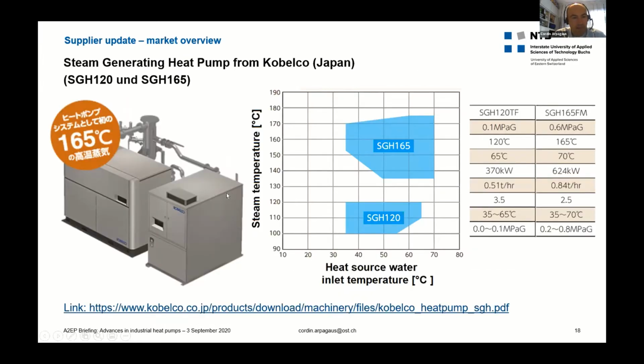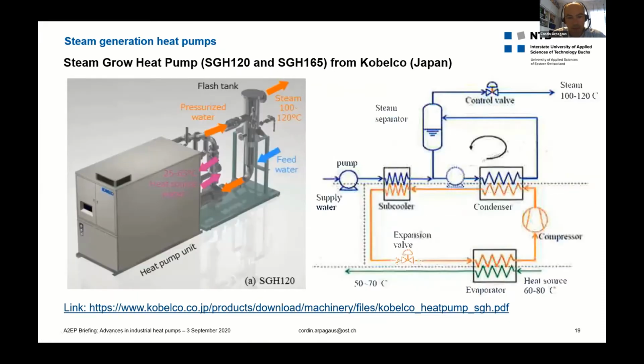This is another graph of the Kobelco steam generating heat pump from Japan. It shows the operating map as a function of the temperature of the steam and as a function of the heat source inlet temperature. So this model can reach almost 170 degrees at a 70 degree heat source. The COPs are around 2.5 to 3.5, and this system can produce 0.5 tons of steam per hour. Here again, I will skip that because of time reasons.